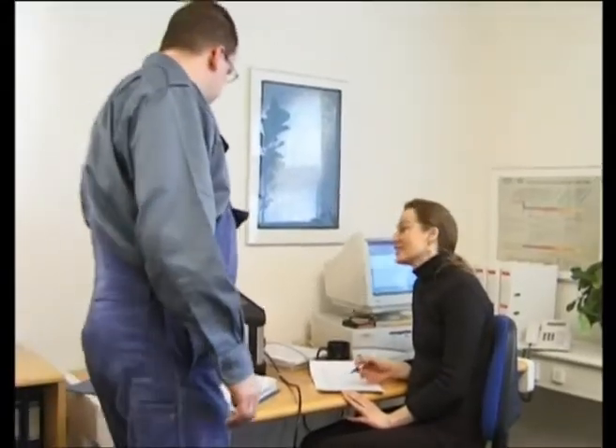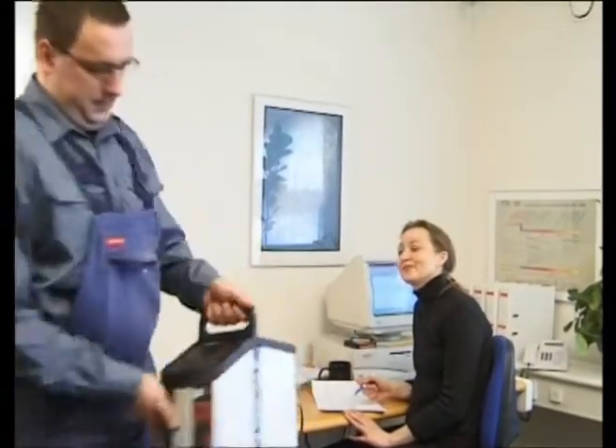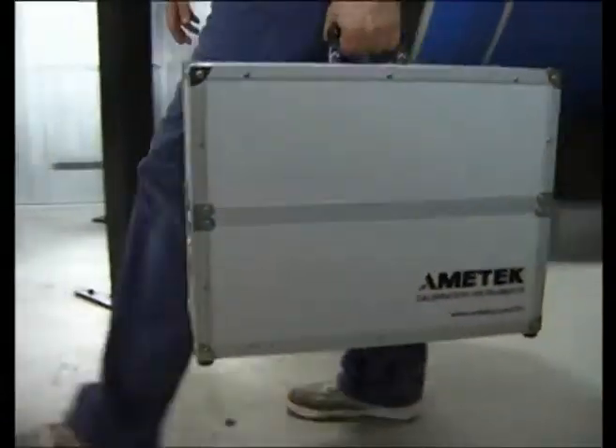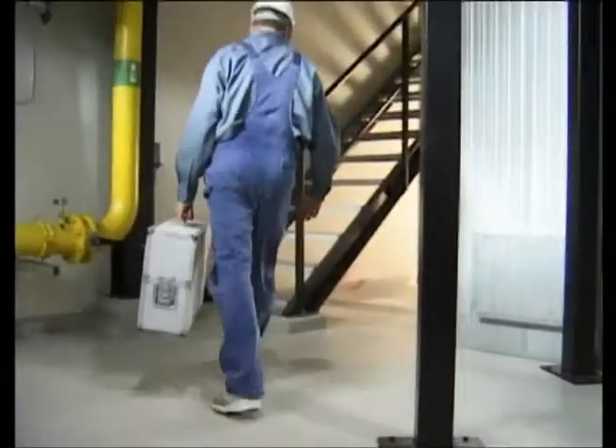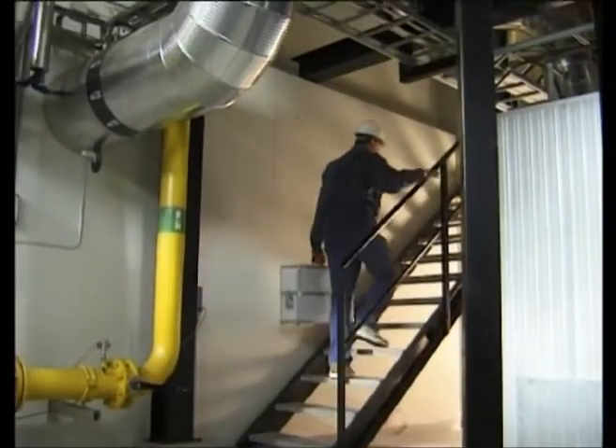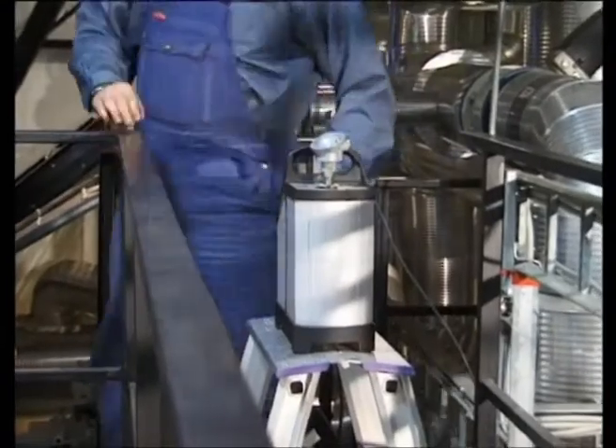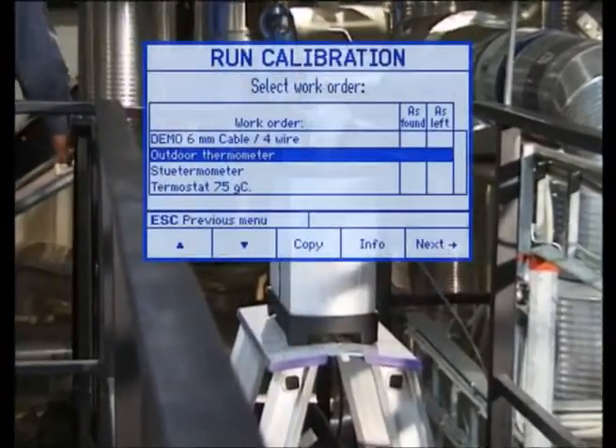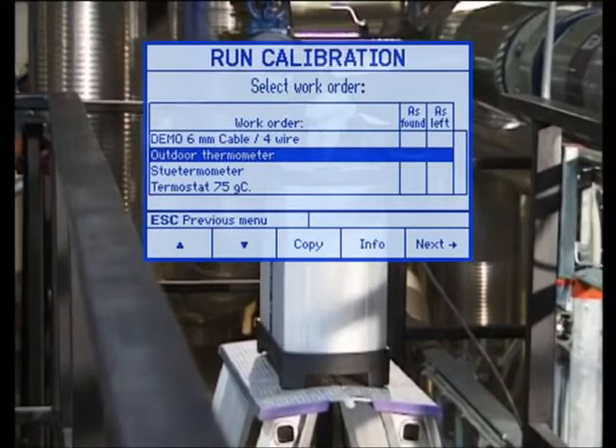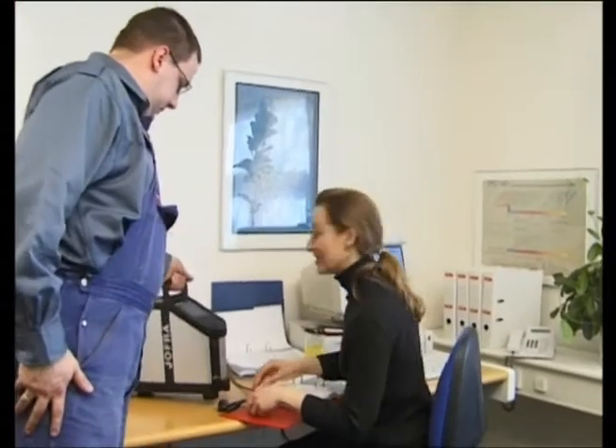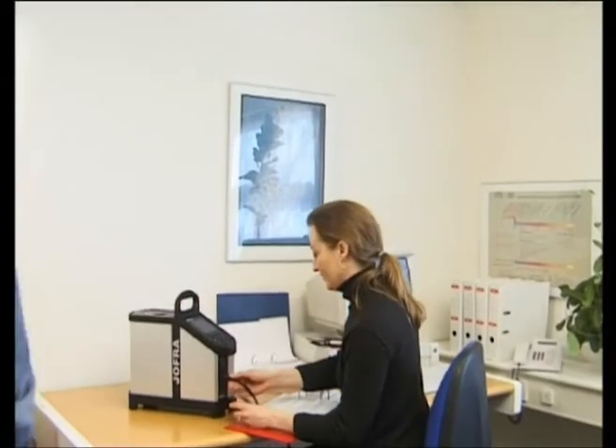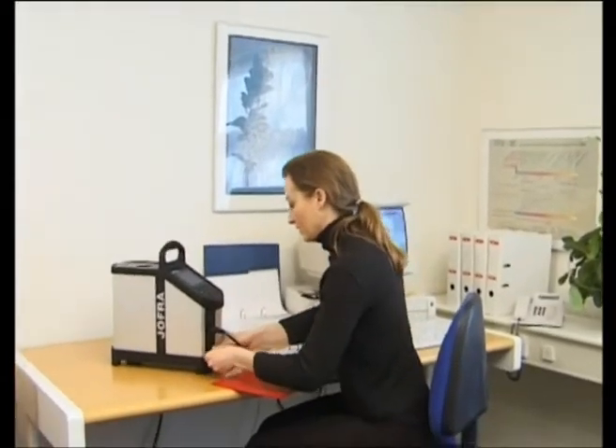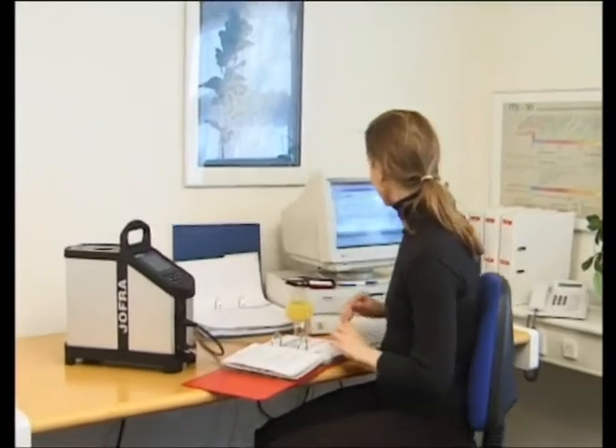First, the Jofra ATC calibrator is able to operate as a standalone calibrator using complex routines. Second, personnel who are not authorized to alter a calibration routine may operate the unit using a pre-programmed test sequence. Upon completion of the calibrations, you may upload the data to the PC for post-processing and printing of certificates. All of the calibration data gathered remains intact and is now stored on your computer.